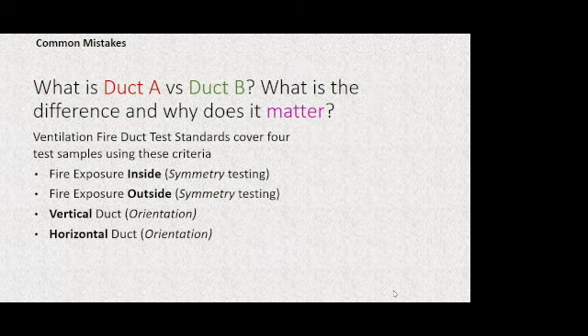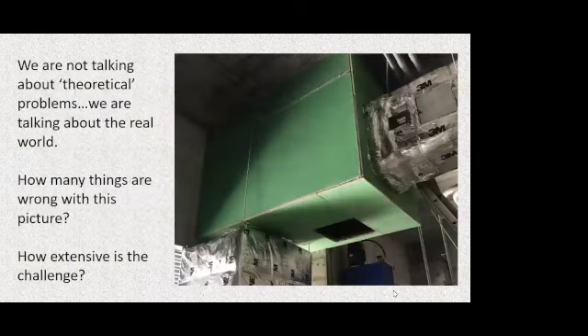Because we have to test fire inside and fire outside to meet the symmetry testing requirements of the building code. And we have to test it vertically and we have to test it horizontally if both orientations of ductwork are going to flow through our building. That's a completely tested product.